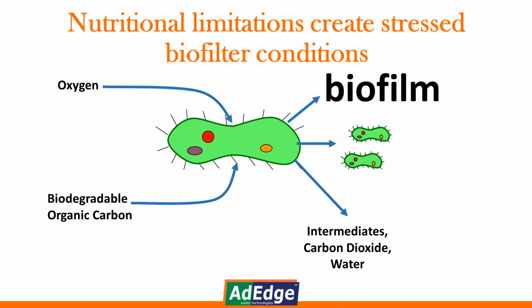If you do have some nutritional limitations, you can create some stress for the biofilters. And so this is something that we will monitor closely, and the chemical feed systems all have control built into them. So if there were an acetic acid pump failure or something like that, we would know very quickly and the operator would be alerted so they could maintain that. The key for effective operation is to keep some biofilm, a healthy layer, but not too much, which causes the pressure differential buildup quicker in the vessels.